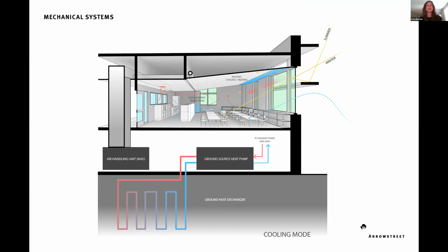This is a little schematic showing a typical classroom. We have radiant heating and cooling in a panel on the ceiling at the exterior wall, and an exhaust point closer into the corridor. We have displacement ventilation, which supplies air low into the space, really in the occupied zone. It allows for a quieter system because the velocity is lower, it's more thermally comfortable, and it provides better air quality since fresh air is supplied in the breathing zone and then stratifies and exhausts to the ceiling.